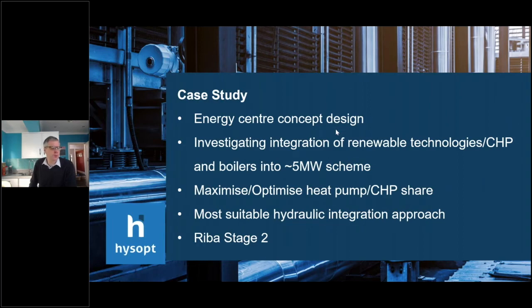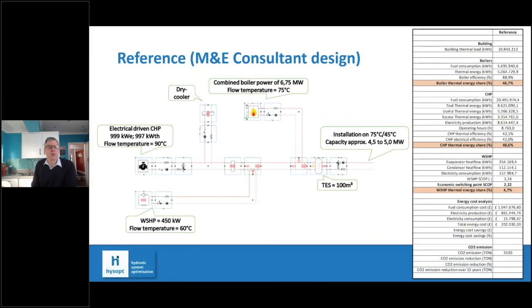The first little model here is a representation in our software of the consultant's RIBA Stage 2 design. At the bottom left-hand corner there's a 450 kilowatt water source heat pump. Above that you have a 1 megawatt CHP engine. And at the top there you have an array of gas boilers, just put as one boiler here, but it's about 5 megawatts of gas boilers. And we have some thermal storage on that system as well.